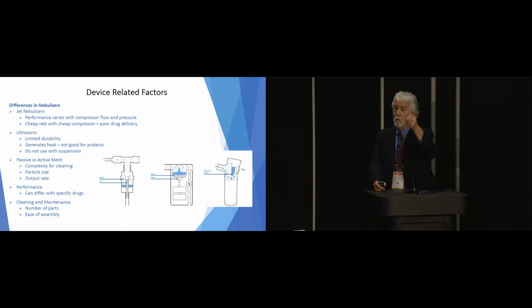The same nebulizer that works in the emergency room when it's hooked up to oxygen or air at 50 psi and makes these really small particles, when you put it into a cheap compressor that's only doing 5 or 6 psi, you now have boulders coming out and it all goes to the back of the throat. So it's not going to be as effective as a device.